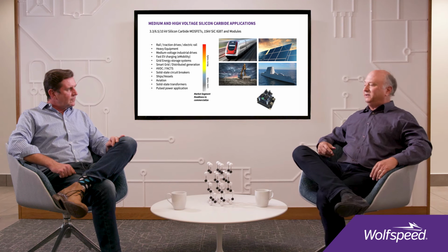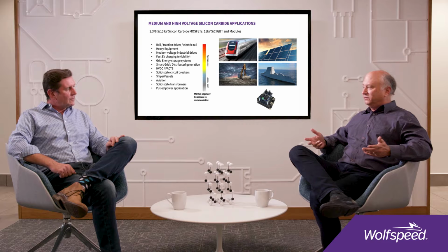So above 650 volts, it's really mostly IGBTs in silicon. In silicon carbide, it has 10 times higher breakdown electric field, so that crossover point is basically about 10 times higher. So 6.5 kilovolts, that would be a MOSFET. At 10 kilovolts, it can be a MOSFET if you want high frequencies, or an IGBT if you want lower frequencies and lower conduction losses or more current. So 10 kV is kind of a crossover point, and it depends on the application you're trying to fill. Above that, the MOSFETs get too resistive and too large, and we see IGBTs above that.